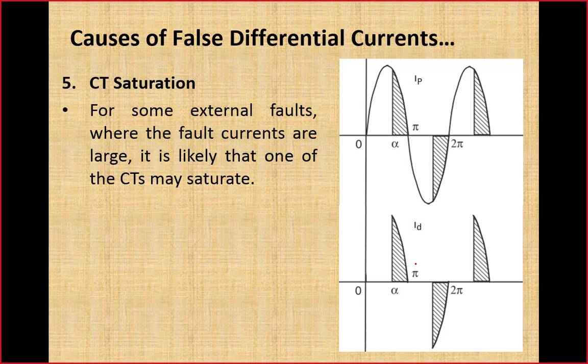So here is the difference current, the difference of the sinusoidal current and the current at the secondary side of the saturated CT, that will flow toward the differential branch. Now if we perform the harmonic analysis of this current which is passing through the differential branch, we can see this current is symmetric about the horizontal axis. Due to this reason, even harmonics are not present, but this time this is not an even function.